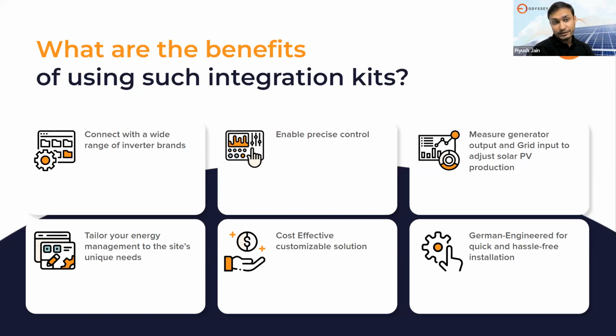There is another advantage, that the customer can proactively get the troubleshooting or reduce the downtime by estimating the estimated fuel availability in the generator. For example, if in a day or two we are going to experience an outage, we have to keep our fuel level up for the diesel generator so that we can cope with the power supply at a reliable rate.